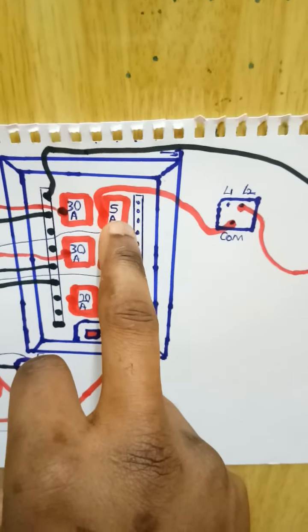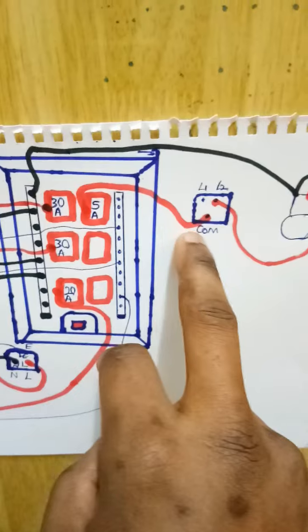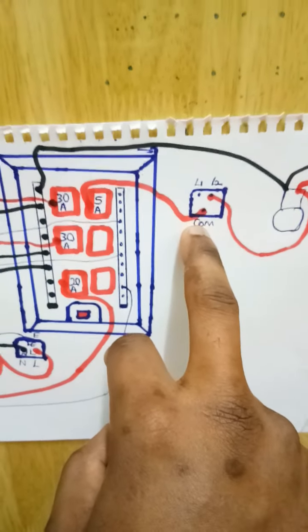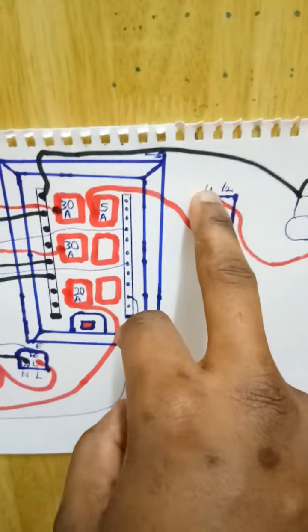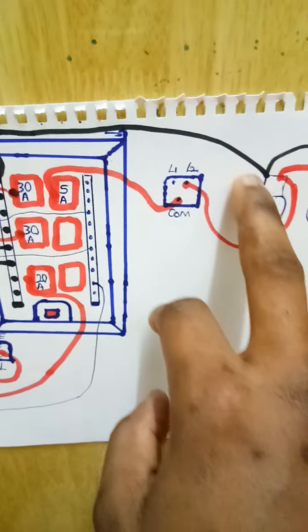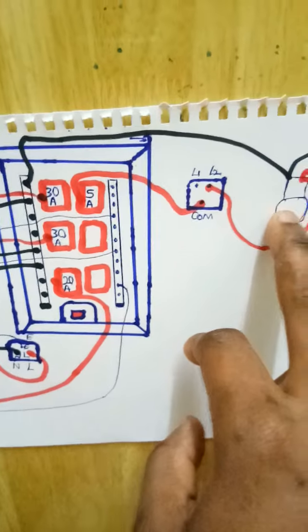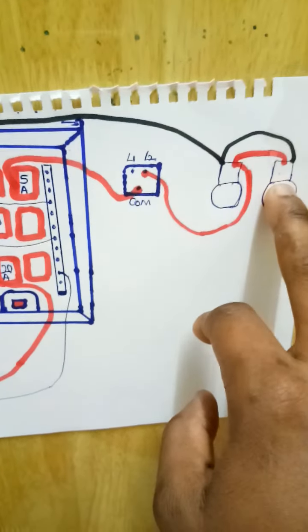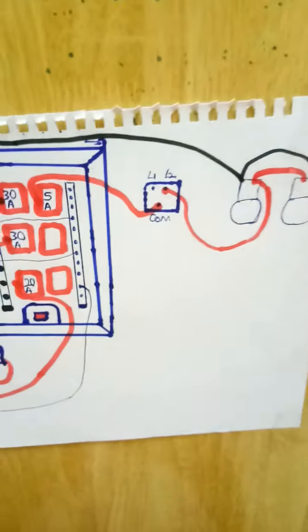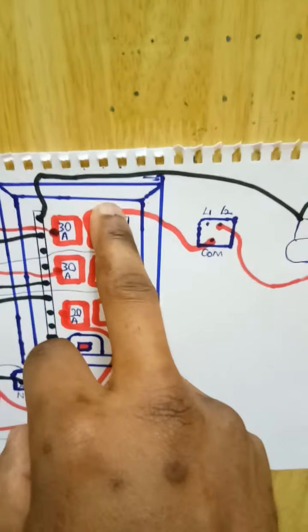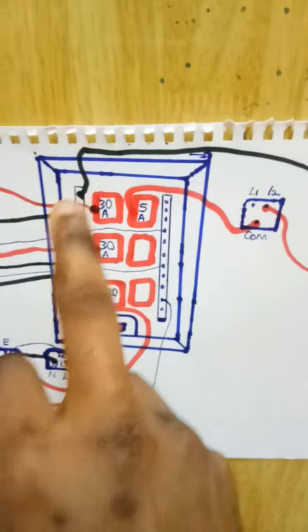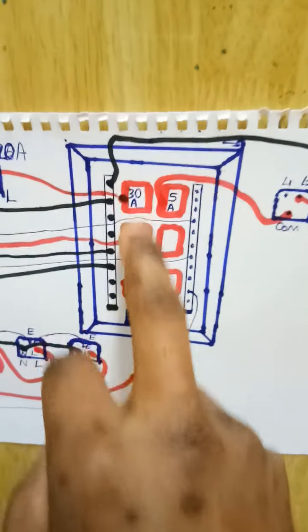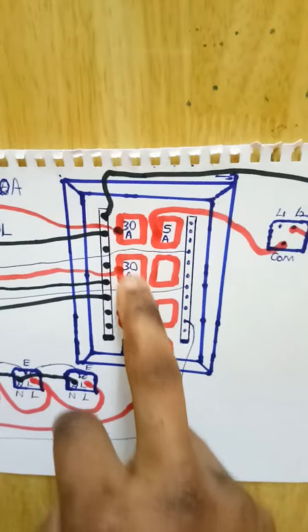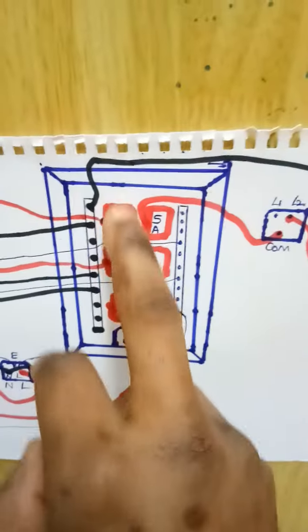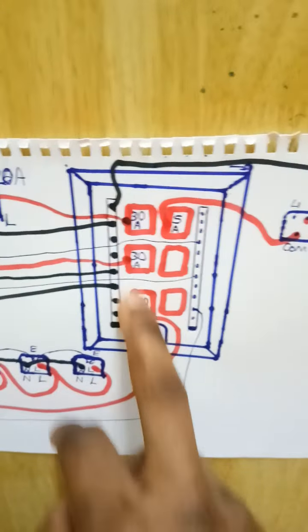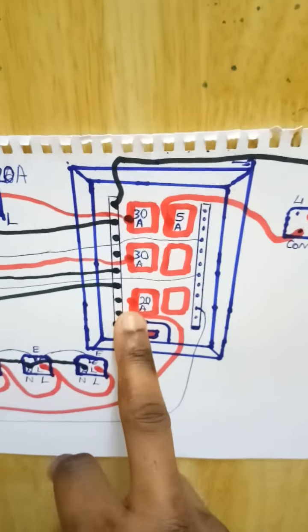From the circuit breaker, you take the live, you drop it to the common of the switch, and you take from either L1 or L2 to the lighting points to feed the lighting points. If there is a problem here, it will not affect these other circuits. This is why this distribution board is very safe and reliable. It's very convenient for electrical installation.